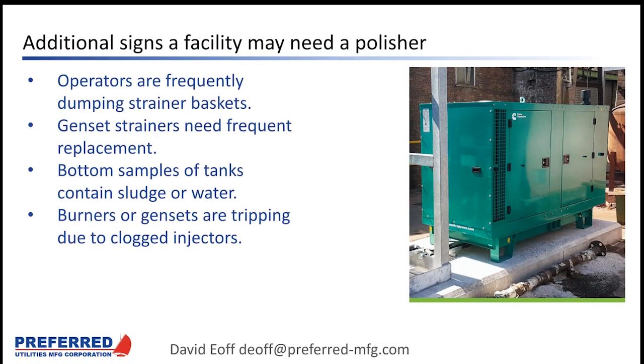There are other operational symptoms that your fuel tanks are accumulating a lot of water and can benefit from a polisher. These include your operators are frequently dumping strainer baskets. Genset strainers need frequent replacement. And you've got to look at what's in these strainer baskets. Sometimes you'll find construction debris. If the pipe wasn't cleaned out really well when it was put together, you'll get little burrs and weld slag. Sometimes you get little pieces of Teflon tape or pipe dope.